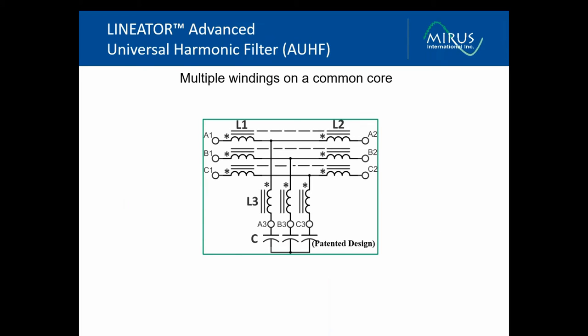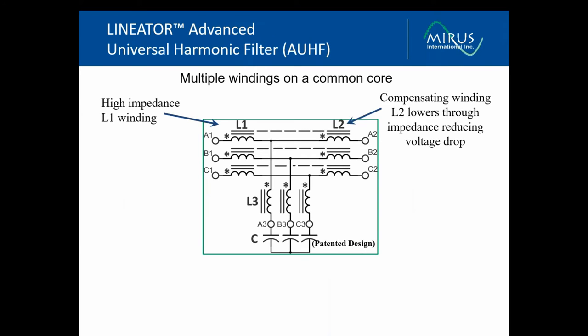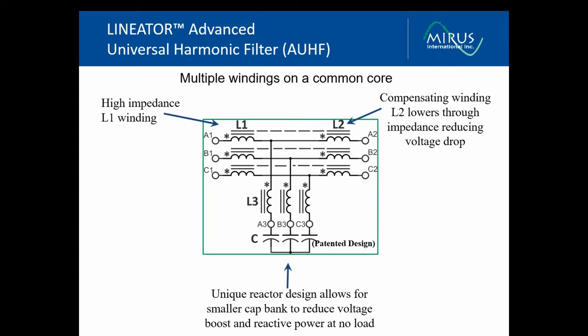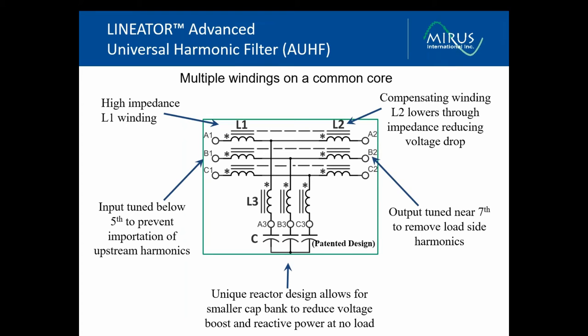Here's the schematic diagram. On the input side, we have a high impedance blocking reactor. On the output side, we have a compensating reactor, which allows us to get more effect in reducing harmonics without introducing too much of a voltage drop. The branch circuit is a tuned circuit, and it's set up so that the capacitive reactance is extremely low, so we're compatible with generators. We're tuned below the fifth harmonic on the input side so that we don't attract harmonics from other loads connected on the system or background voltage distortion. The output is tuned in around the seventh and is targeted to reduce the harmonic currents introduced by the six-pulse variable speed drive.